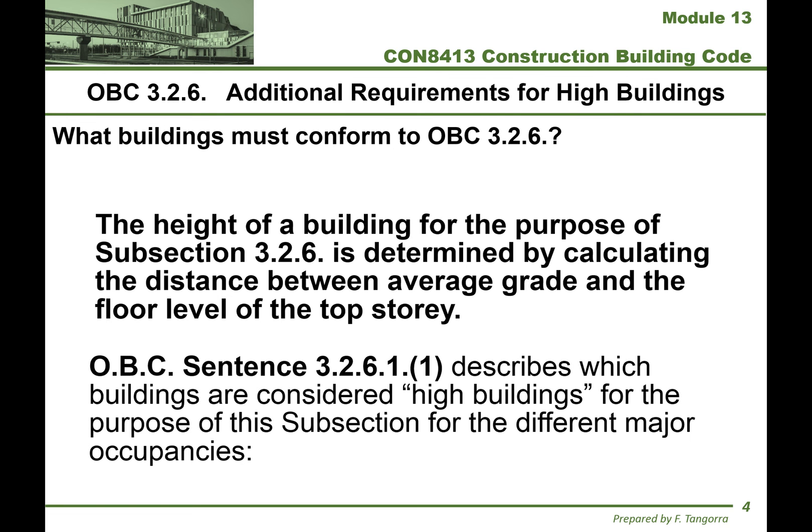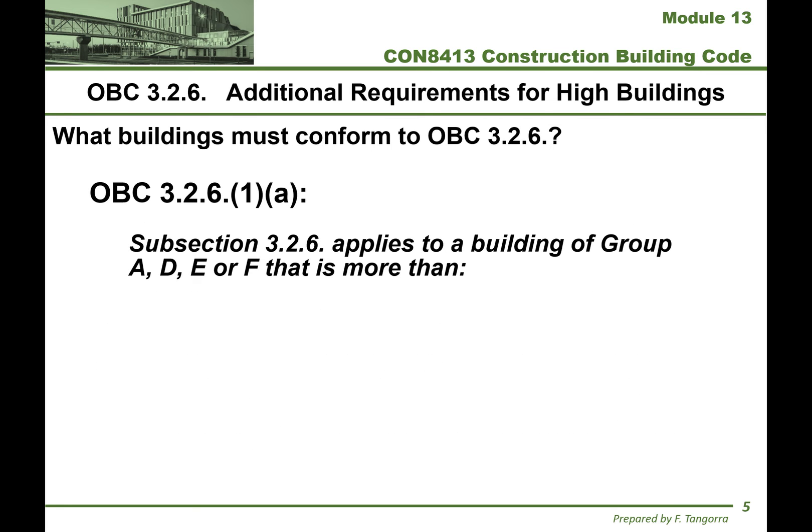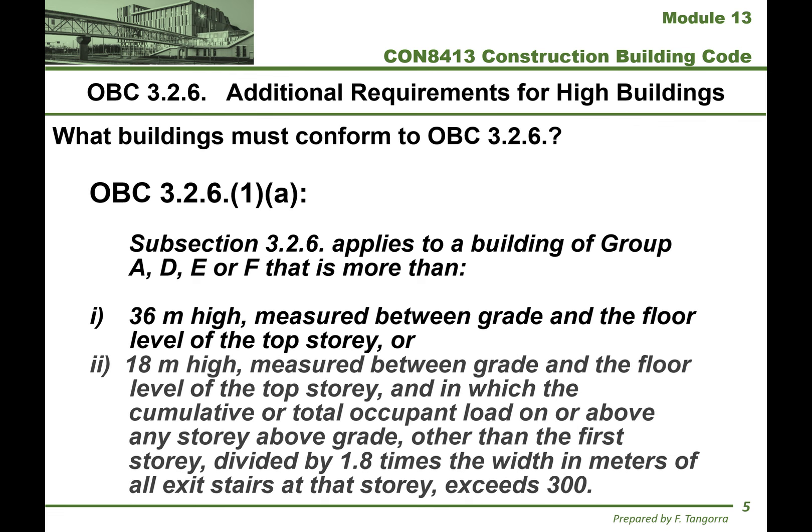Here's what sentence 3.2.6.1.1 actually says — and I'm paraphrasing. High buildings for this subsection depend on occupancies as follows. For groups A, D, E, or F, if the building is 36 meters high or more between grade and the top floor level, it's considered a high building. If it is 18 meters high or more, then you must use a formula that is described in words in the code — I see a 1.8 and a 300, exit stairs, that sort of stuff.